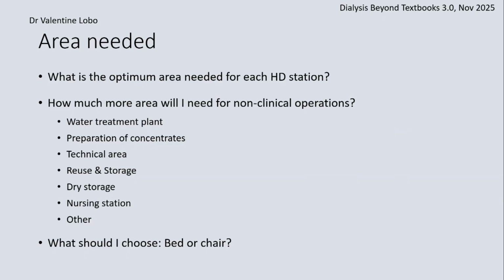It has to be able to accommodate the plant. It has to be able to accommodate the storage tank, if there is a storage tank, and it has to have space again for moving in equipment that is required for servicing, for preventive maintenance, and for other things. All that space has to be taken into account when planning the area for water preparation of concentrates. So we would advise that the technical area and the area for preparation of concentrates could be combined. That is what we do.